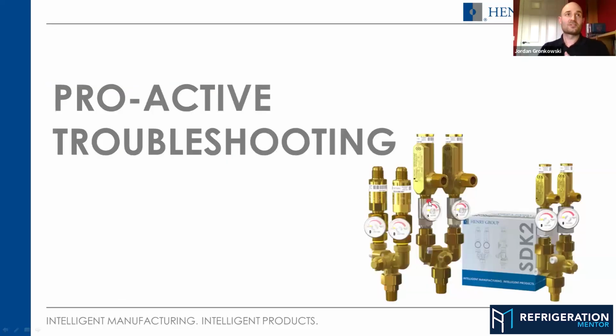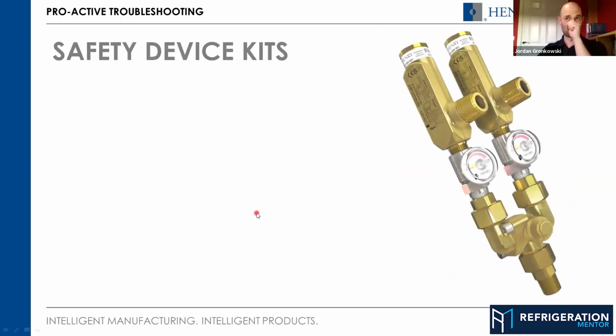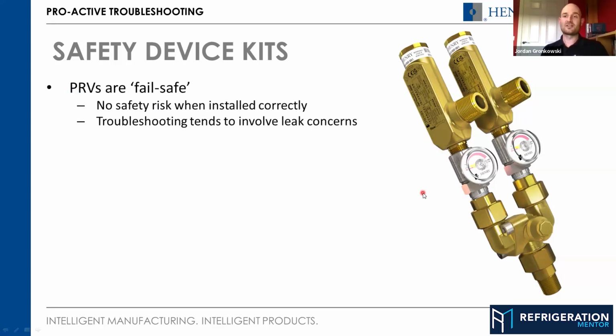So the last section I just want to run through quickly is what I've called proactive troubleshooting for PRVs. So mostly it's the safety device kits that you see on screen here. Again, if you saw Trevor and myself at Chillventa, we covered a little bit of this on the stand. So PRVs in general are fail-safe devices. So they are designed so that if any individual part of the valve breaks, they're going to open and vent.